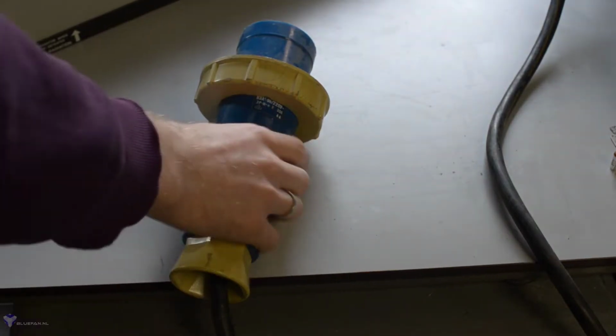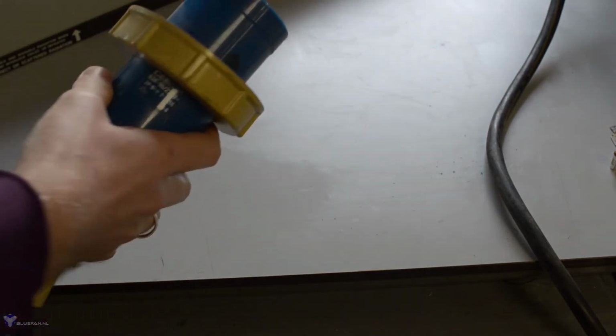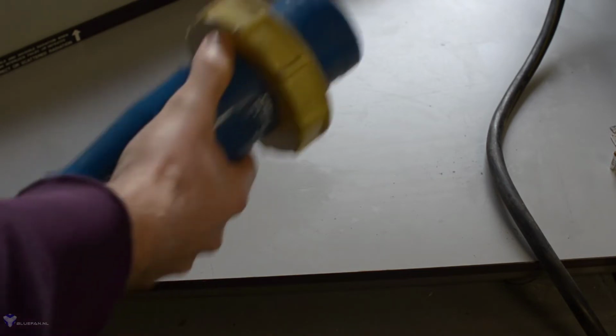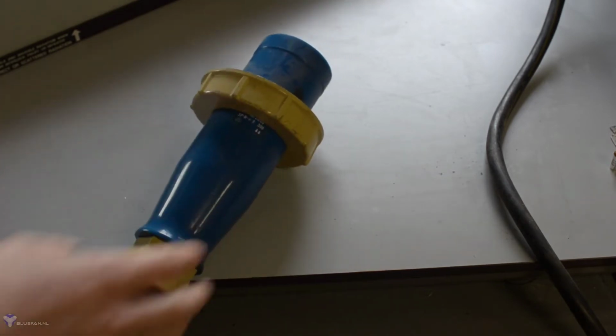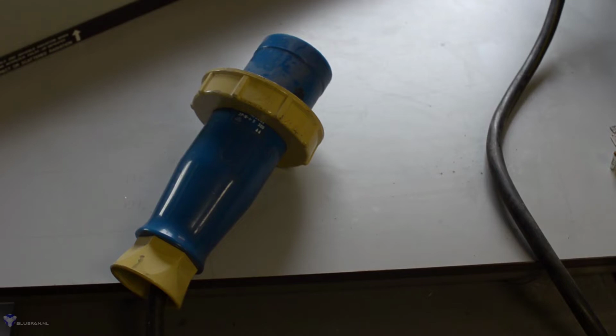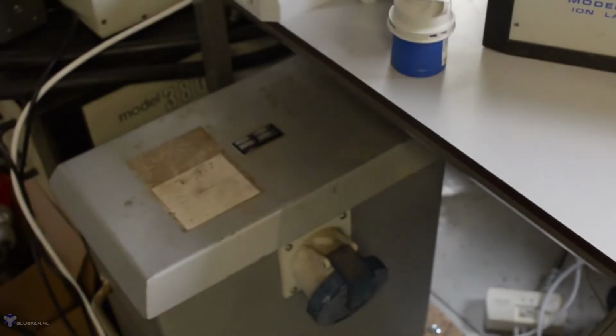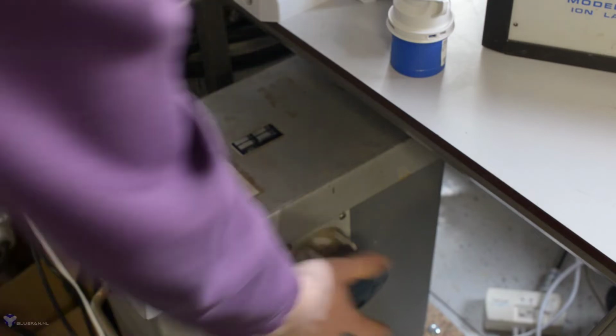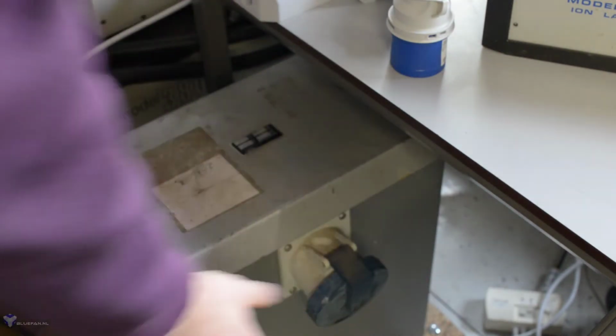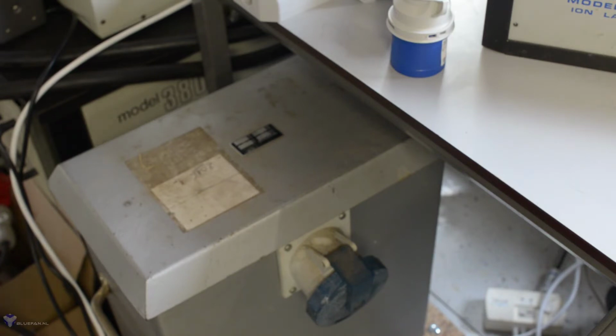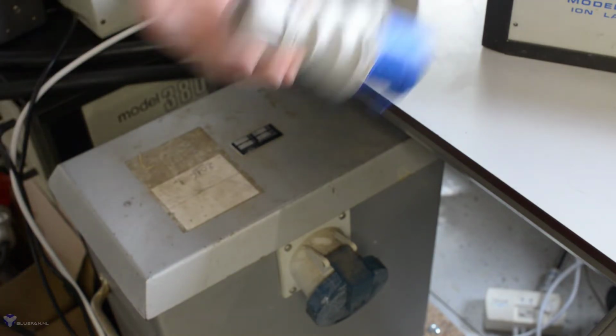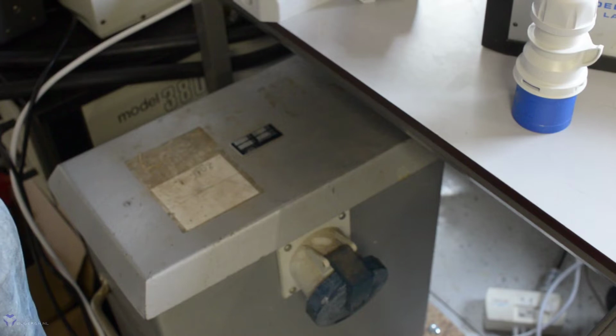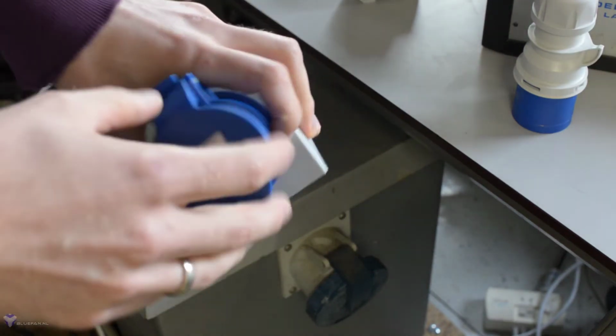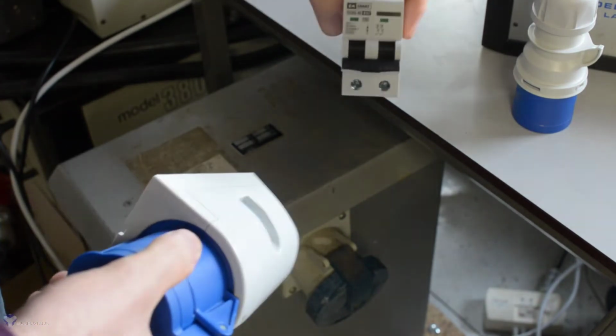Now the laser has this massive 63 amp 5-pin plug, and it's quite overkill because if you read on the back of the laser, it only can draw a maximum of 32 amp on a single phase. Now I have a transformer to supply that current. It is a 3-phase transformer, but it has a 4-pin socket, and that matches the other argon lasers that I have, but at the moment it's a bit inconvenient. So my plan is to put a single phase 32 amp plug on the laser and the matching wall socket on the transformer, of course with an appropriate circuit breaker.